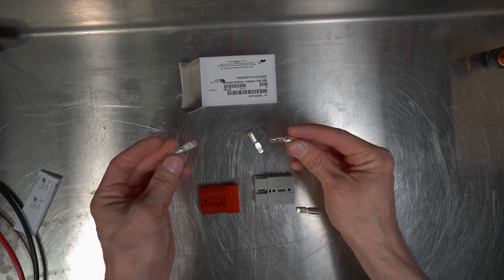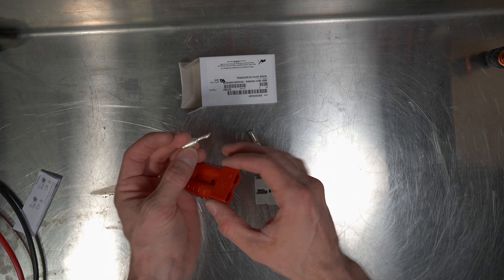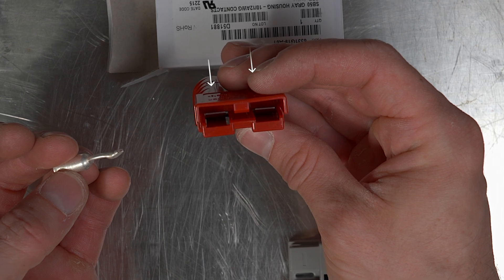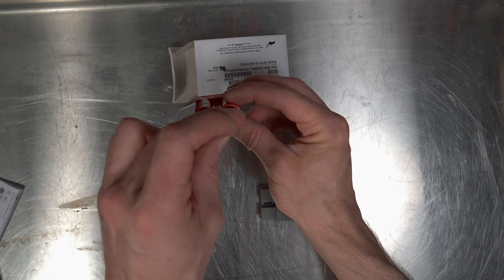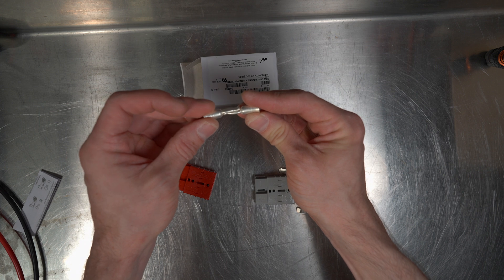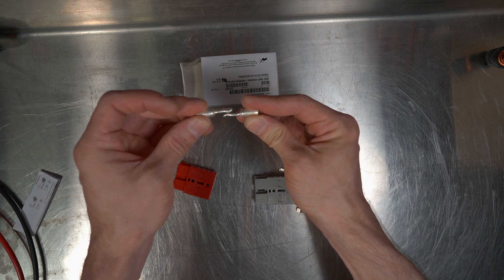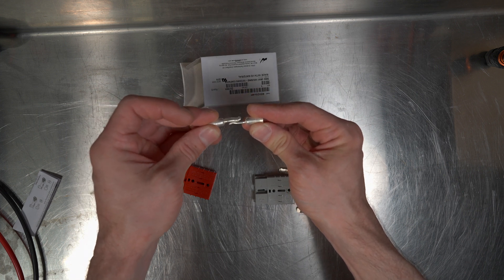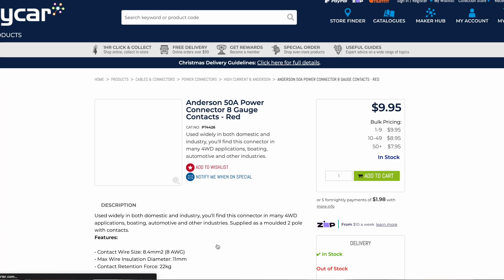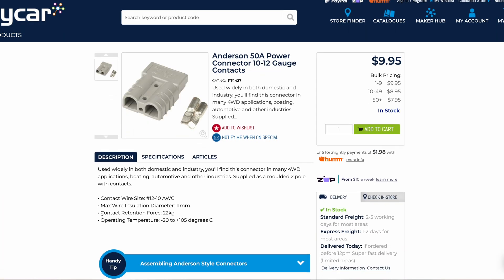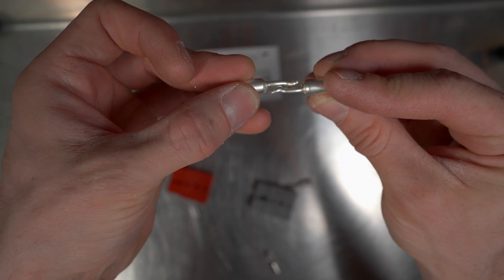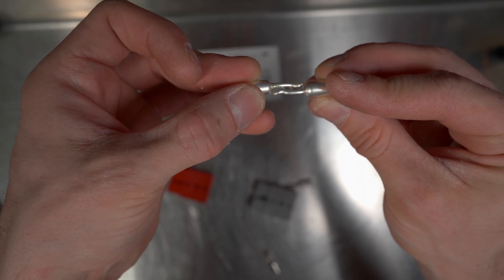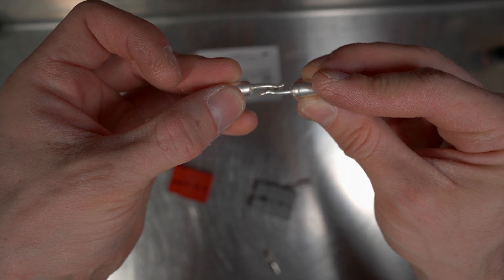Now what happens inside the Anderson plug is you have two contacts in there that are spring force. The lug, once it's crimped, pushes in there. The spring force will connect these and hold them against each other like that, with opposing forces acting on each one. To pull the plugs apart, you just pull and overcome that force. So the two opposite ends click over there, that's what holds this together. Stops it from ever coming loose. It won't vibrate loose. There is spring tension on that holding that in.